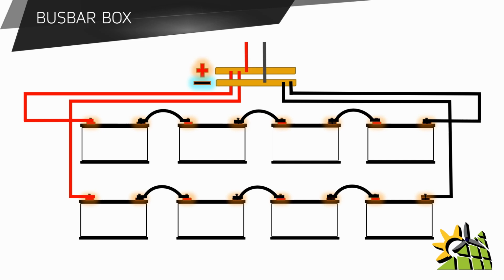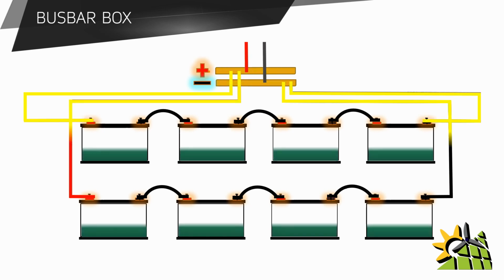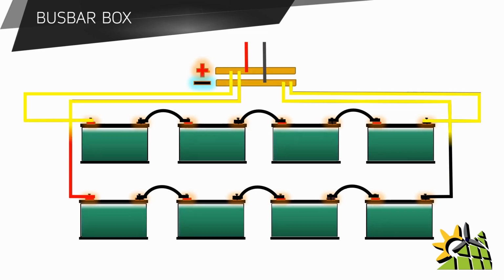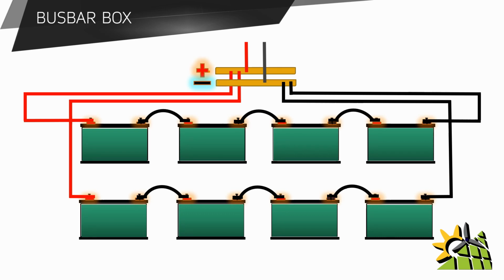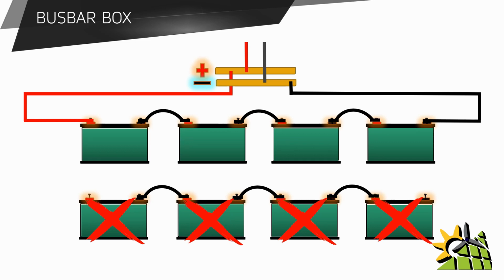You would then have two cables going to the inverter or the battery charger. Now when the batteries are charged, they also will receive equal charge and not be over or undercharged. Now if one battery had to go down, all that you need to do is disconnect that battery bank from the busbar box, and the rest of the batteries will still continue to perform as it was designed for.